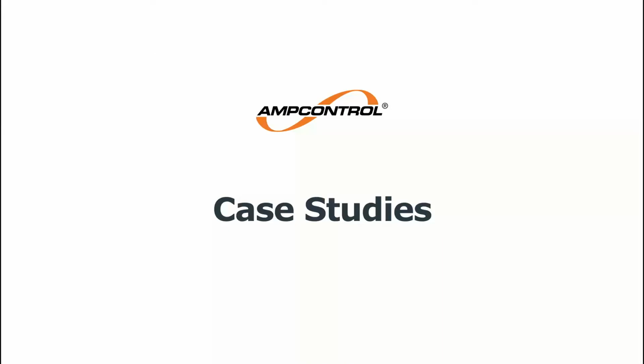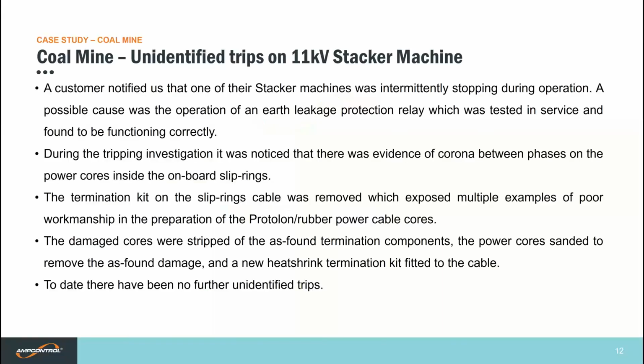Move on now to a couple of the case studies. At a coal mine, we had unidentified trips on an 11 kV stacker machine. The customer noted that one of their stacker machines was intermittently stopping during its operation. A possible cause initially thought was the operation of an earth leakage protection relay, which when tested in service was found to be functionally correct.